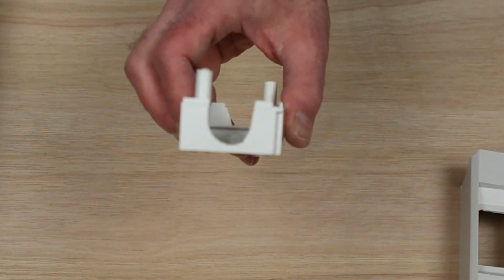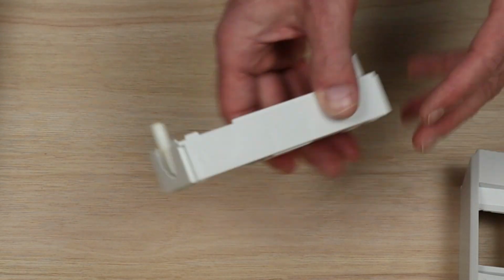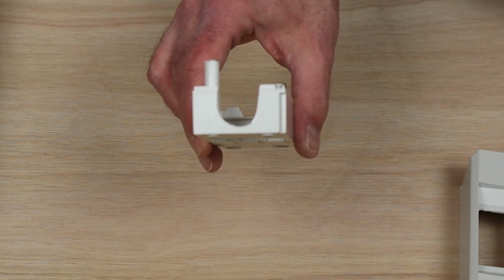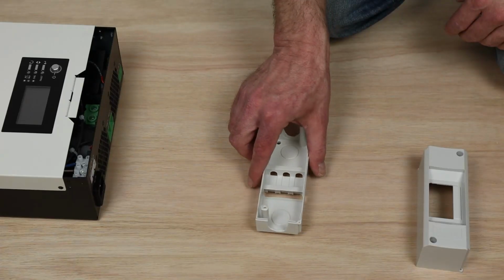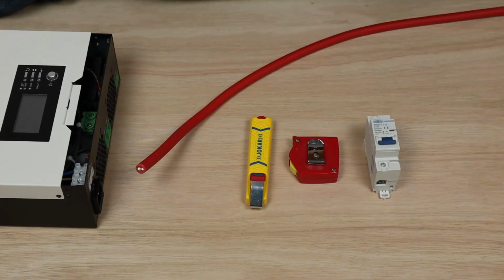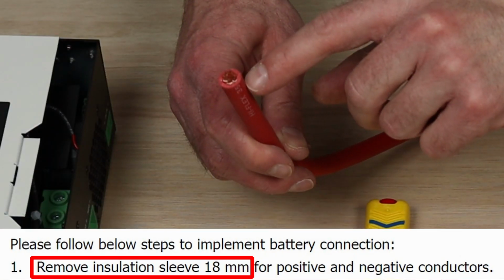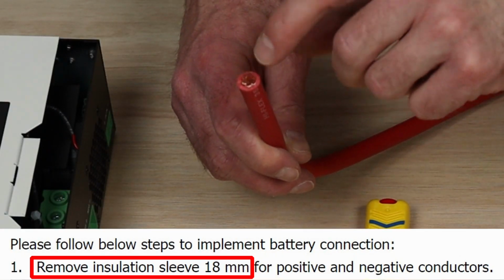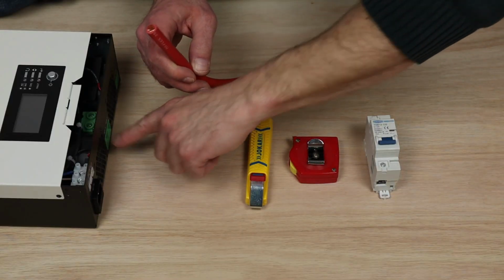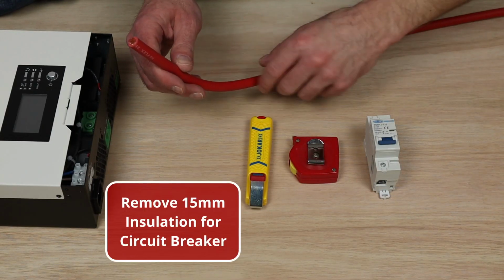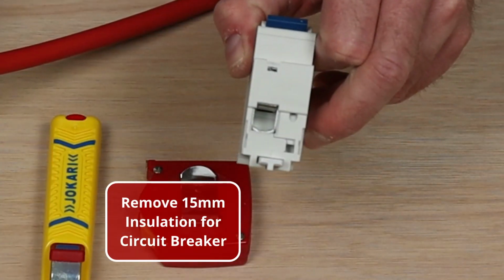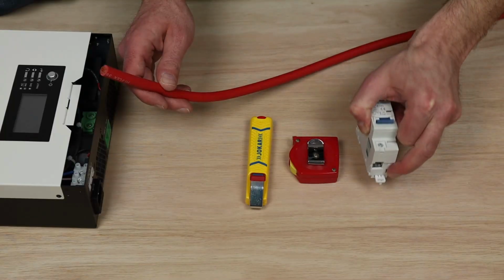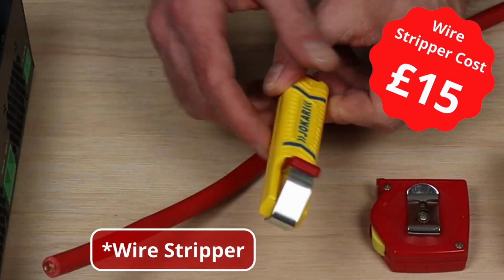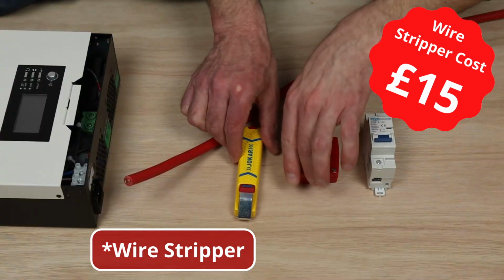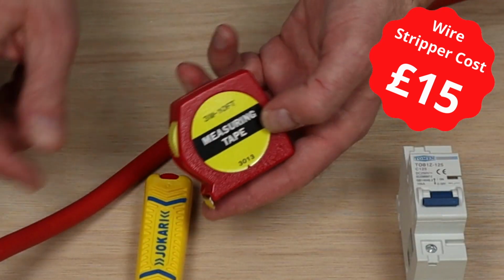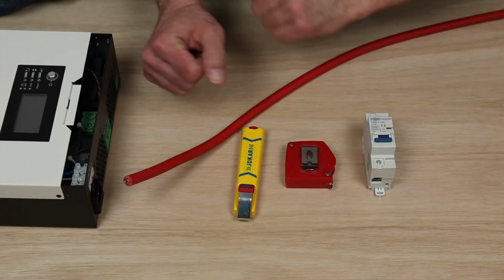I've removed the knockout sections on both ends of this enclosure, so it's ready to get the cable cut and put in here, then mounted on the board. The manual recommends cutting back the insulation by about 18mm to expose the copper wire underneath, to go into the inverter, and I'll do the same at the other end to go into the DC circuit breaker connection. I've got my large gauge wire cutter here, and I'm also going to use a tape measure to make sure I get the right amount on the cable.